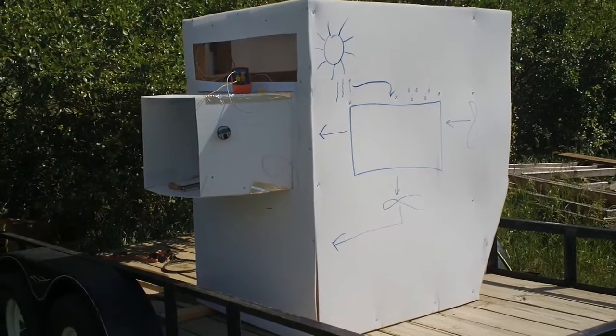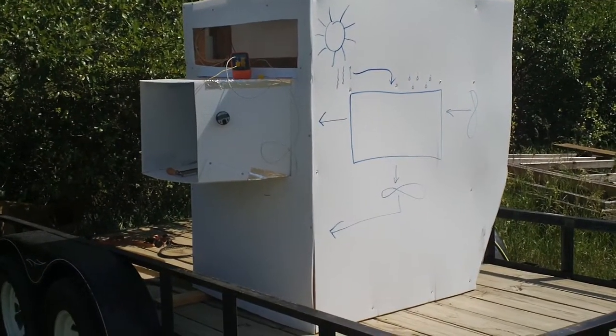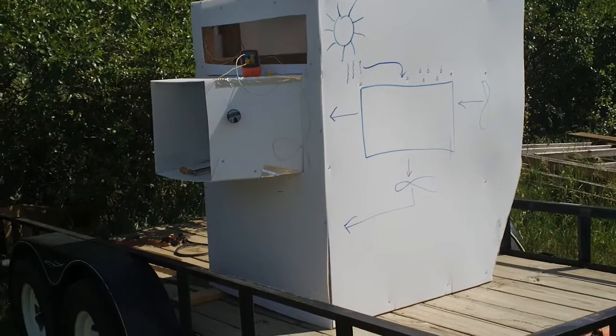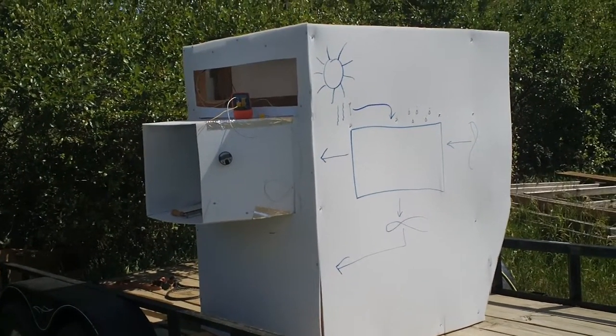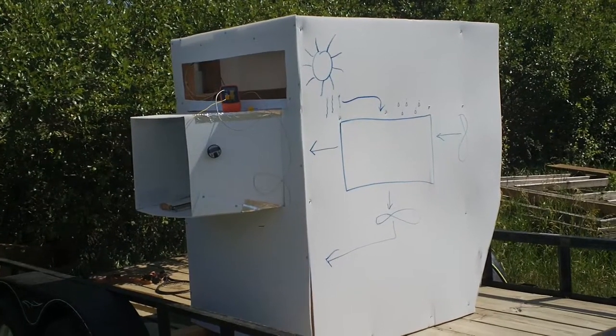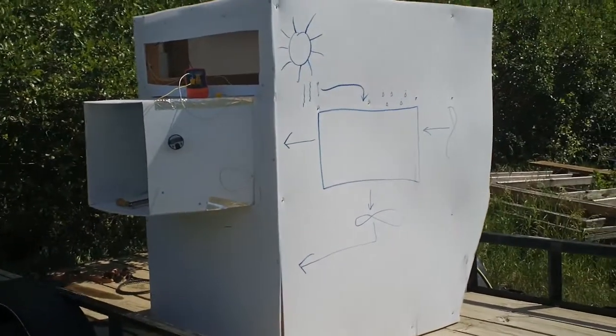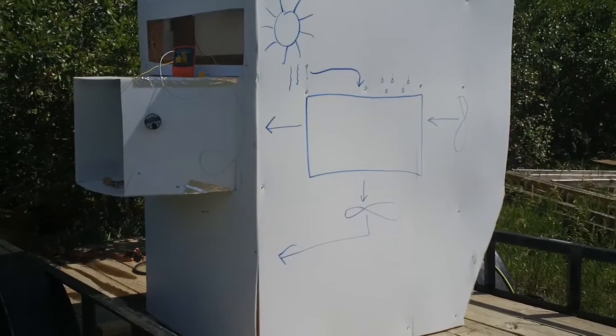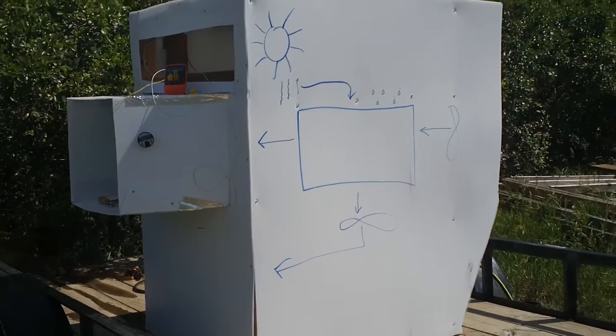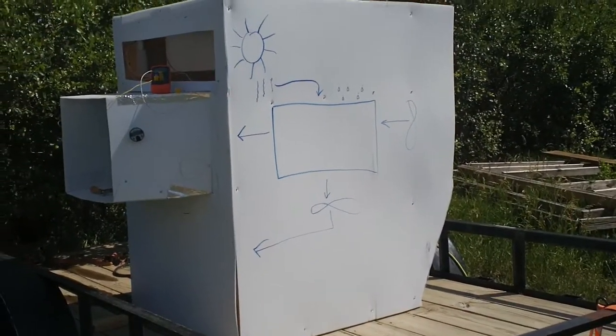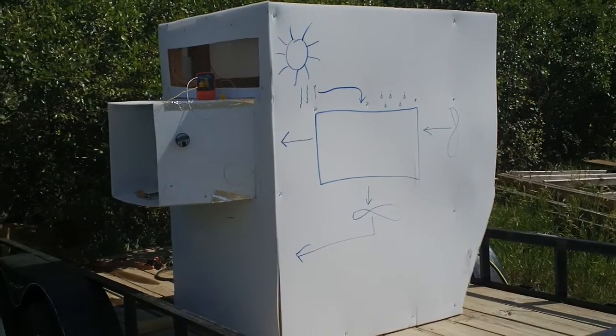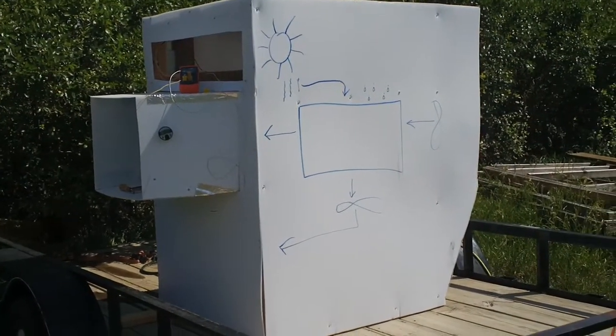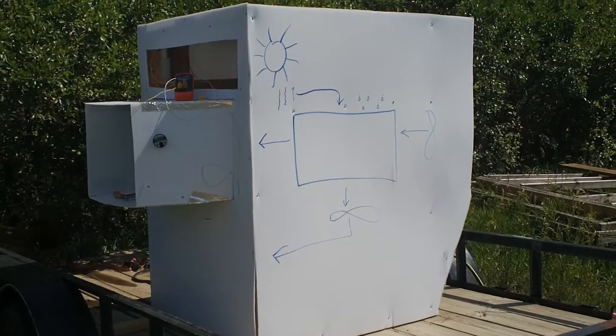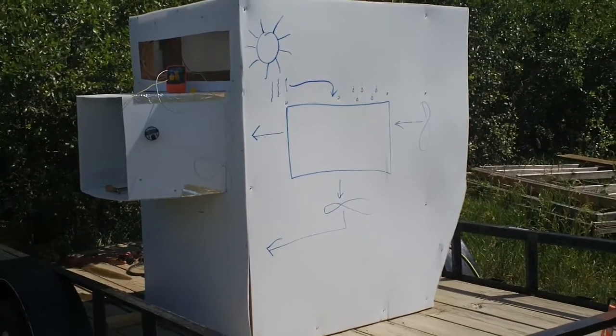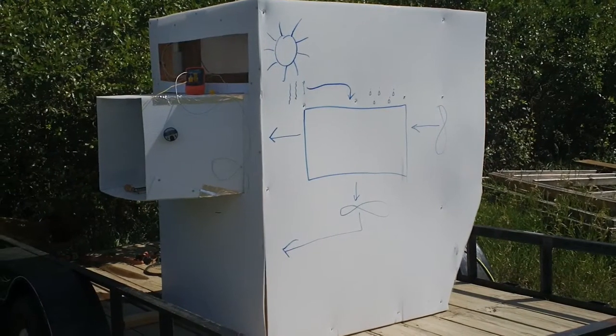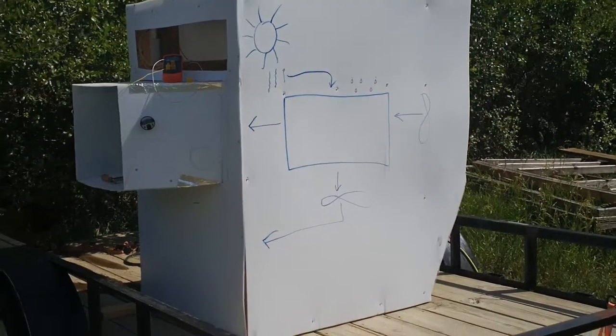That's the nice thing about the split heat exchanger, where we don't have the intersection of any of the air streams, be it the dry side to the wet side or vice versa. There's no intersection, so we can have different behaviors, either pushing or pulling, different speeds, all of that stuff. Another thing to look for is if we have enthalpy sensors in the ambient condition, we can find out exactly what would be the best RPM for our fans to run to maximize the evaporative process, thus delivering a cooler temperature in the product airstream.